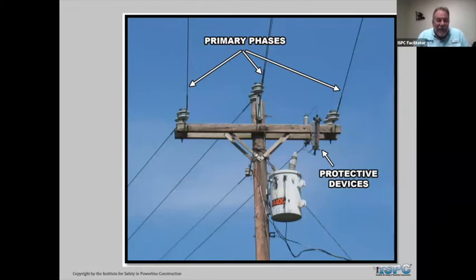So you can see the primary phases. This is a Y system. So a Y system has your 3 primary phases on top, and you can see right about the top of that transformer, a system neutral that is connected. You can't really see it where it's coming back to us, but going off right to the left, there's a little spool that's right there. So a Y system has a system neutral. And like I said, the system neutral is a return current carrying grounded conductor.